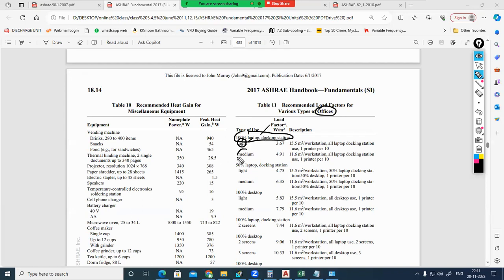Light case and a medium case. Light case means each 15.5 meter square they are considering a workstation. For example, if this is your floor area, each 15.5 meter square of floor area, they will consider one computer, light case. Medium means again the density will increase, the number of computers within the area will increase. The value is 4.91 watt per meter square you should consider, which means each 11.6 meter square of floor area you should consider one computer. Accordingly, that will vary. Correct.